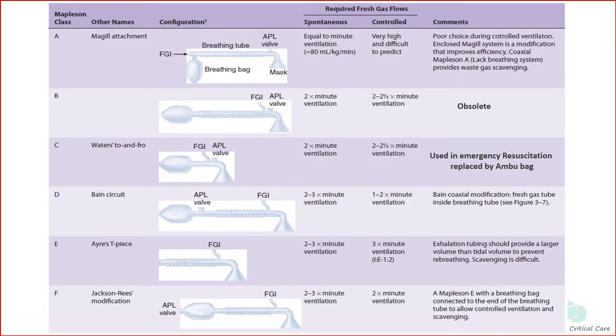Mapleson D, or Bain's circuit, is best for controlled ventilation. Mapleson B is obsolete and C is rarely used today — it was used for emergency resuscitation but has been replaced by an Ambu bag.